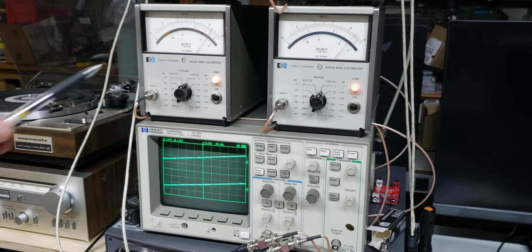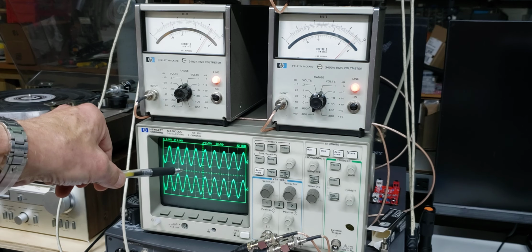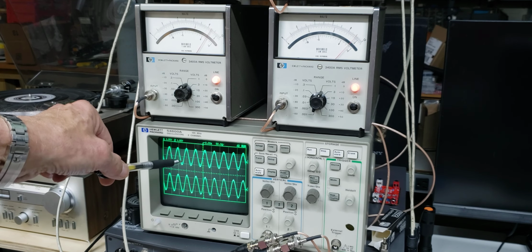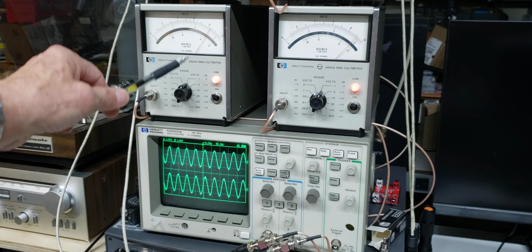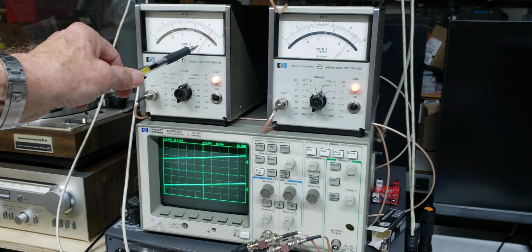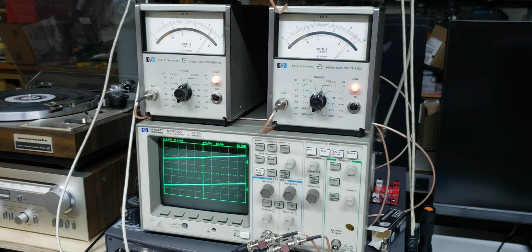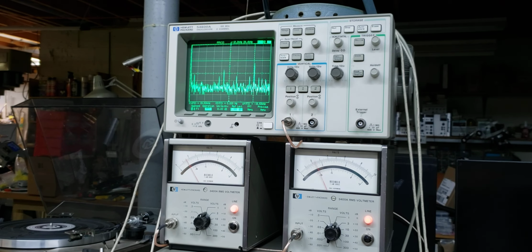See those very small variations now, and watch the screen. Low frequency, high frequency, low frequency, high frequency, low, high, low, high. Almost no change. So I would say that's a pretty good calibration, and it was done in a matter of seconds. Okay, maybe a minute. When you know your procedure, you can do it very quickly. Don't pay attention to the fancy screen above it. We'll get to it in a minute.